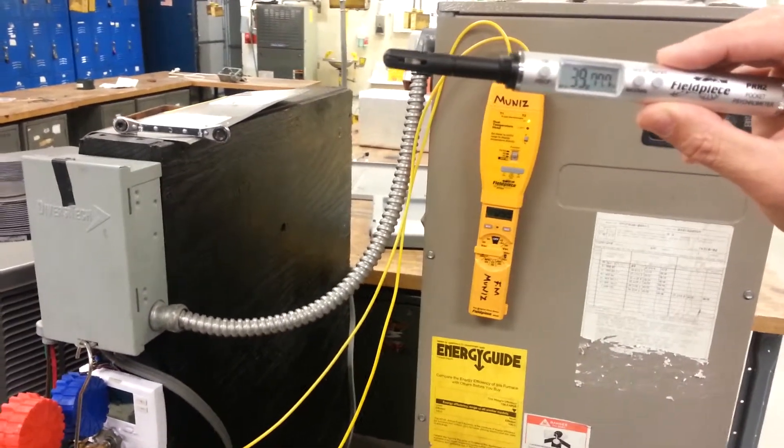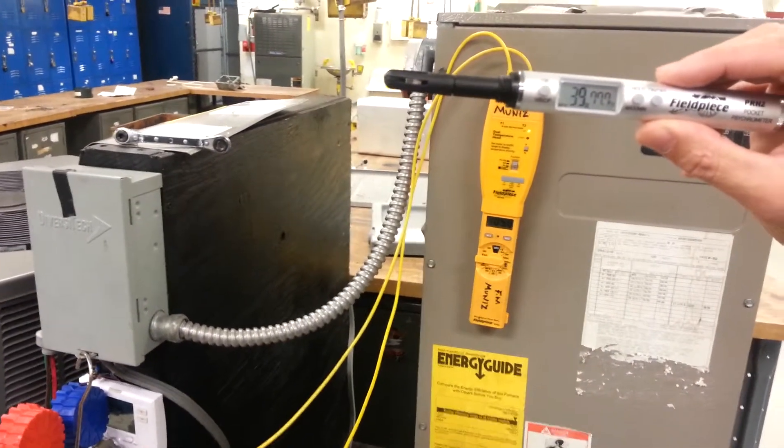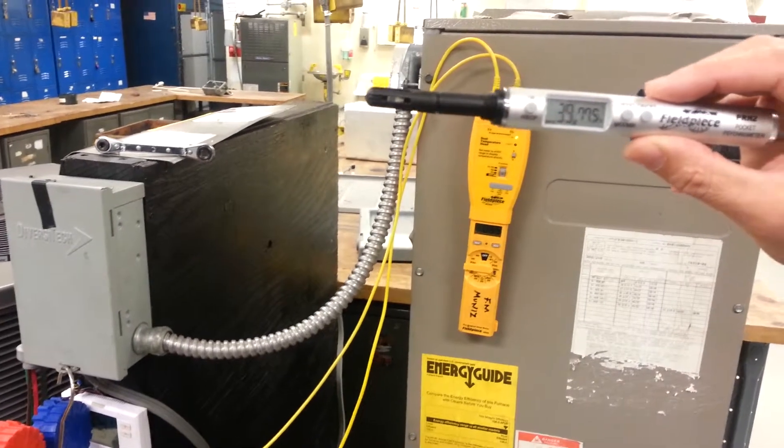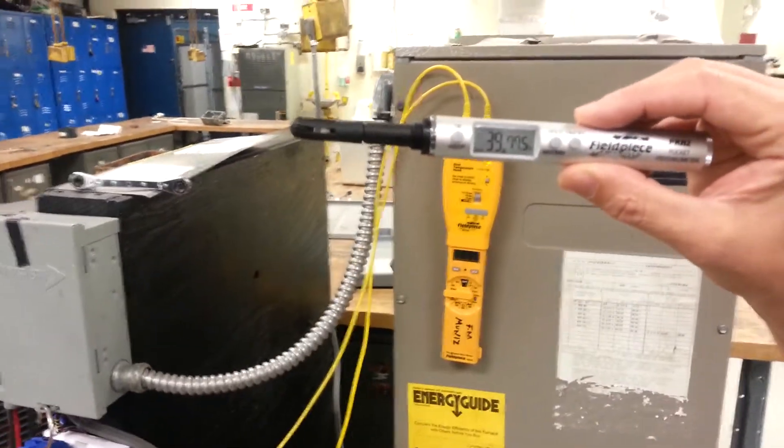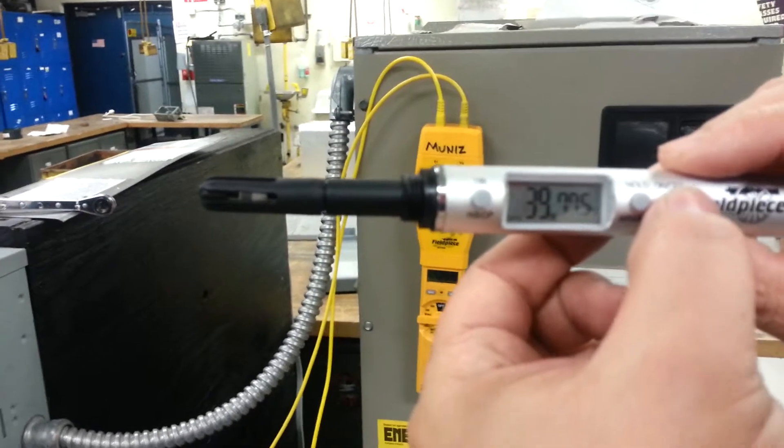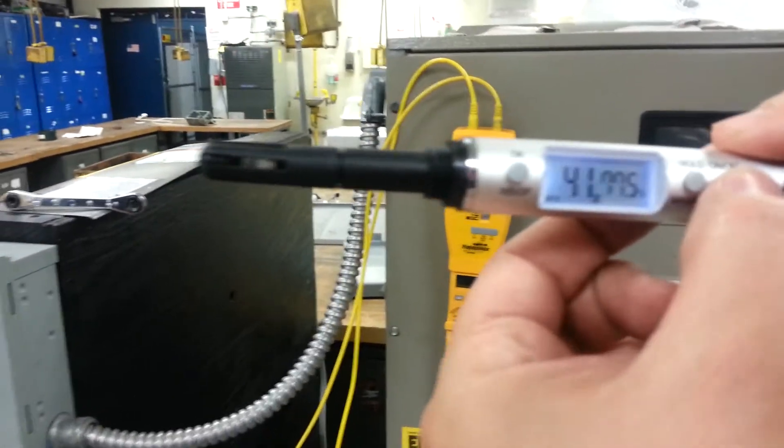Okay, now recording. We're doing the superheat method, so we're getting the indoor wet bulb with the psychrometer right here.